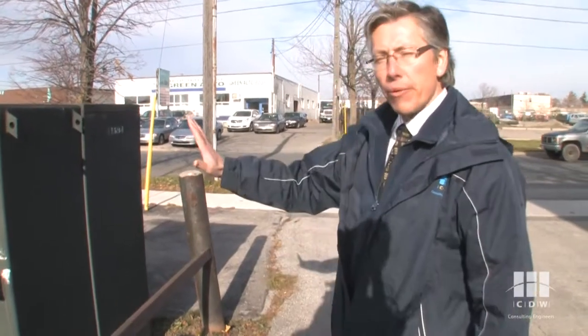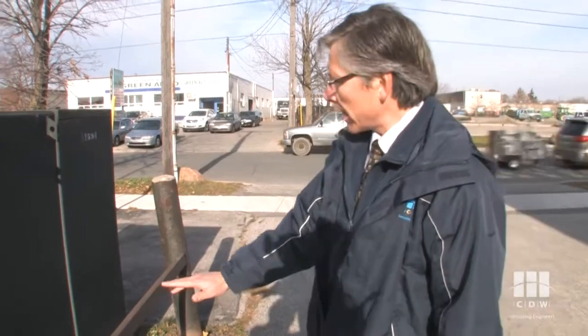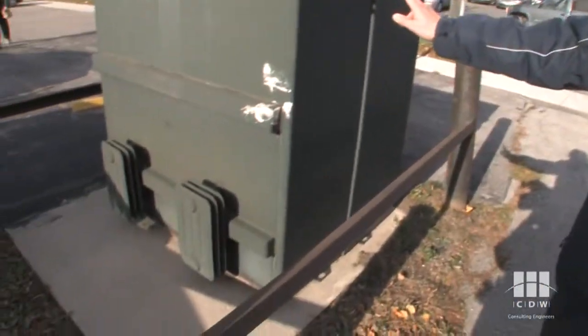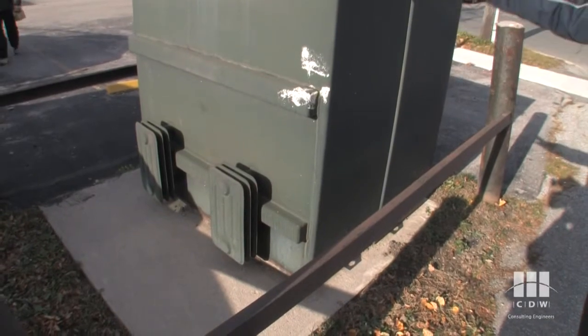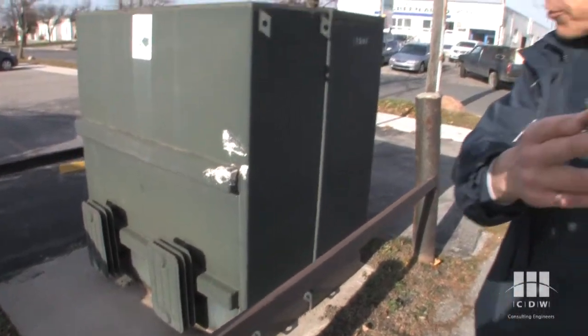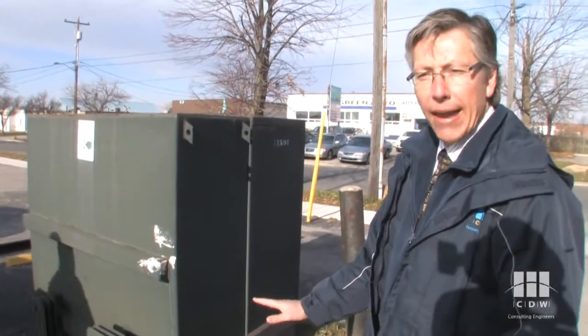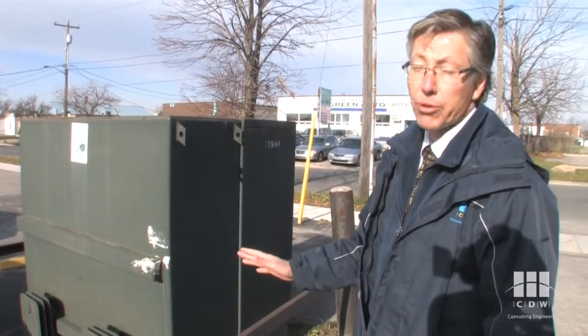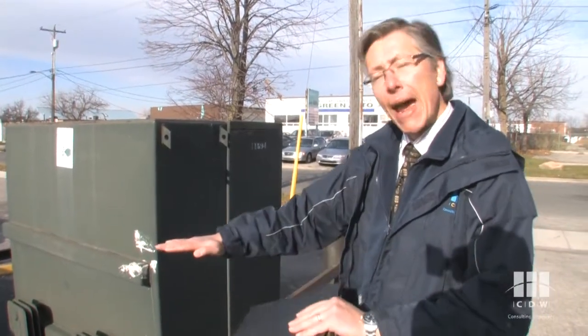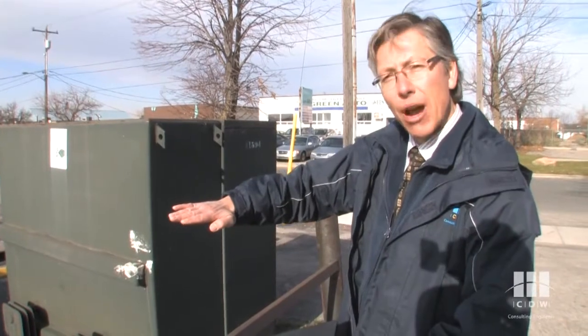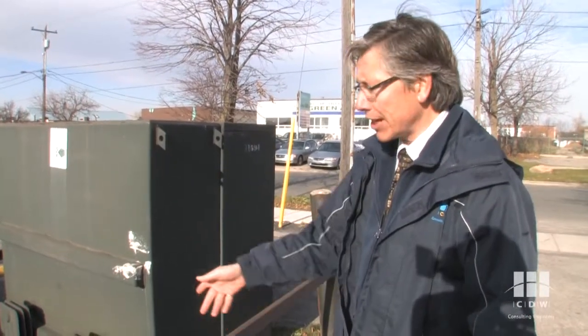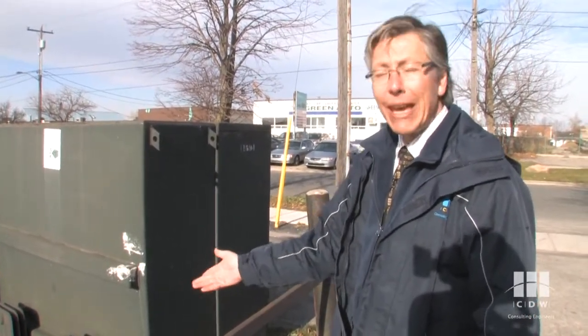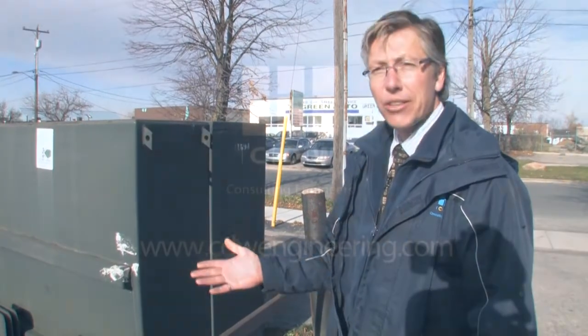So while the transformer is owned by the utility, the owner is actually responsible for the pad that it sits on. Remember, we've got high voltage coming underneath into this transformer, and then voltage coming out into the main electrical room there. So we want to make sure the pad is level, because it would have been poured level originally, but sometimes it settles because it wasn't done properly. That's a concern, because the connections of those wires underground we can't see, but if it's settled, odds are there's a problem there.